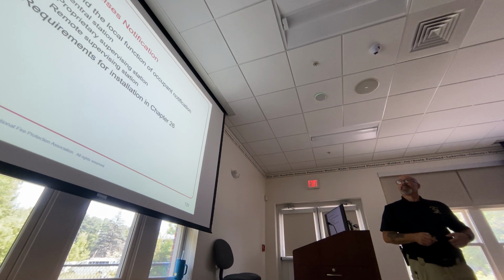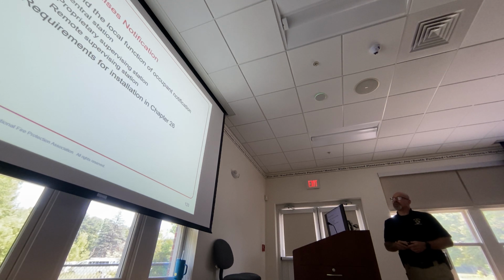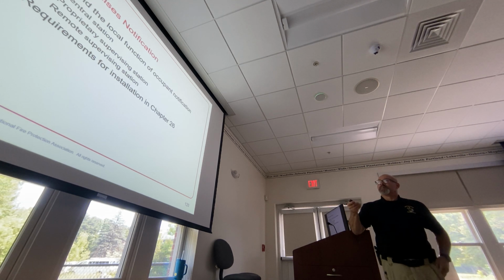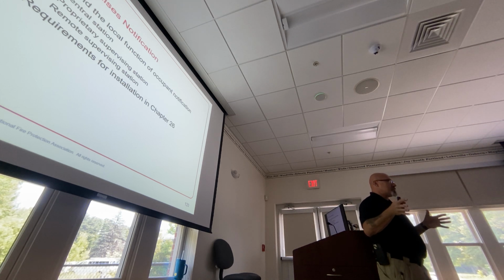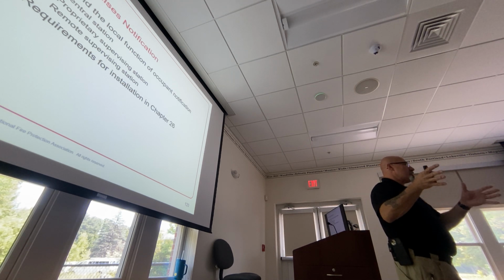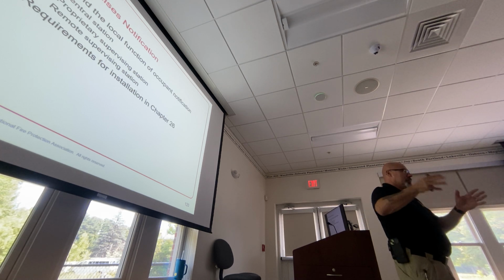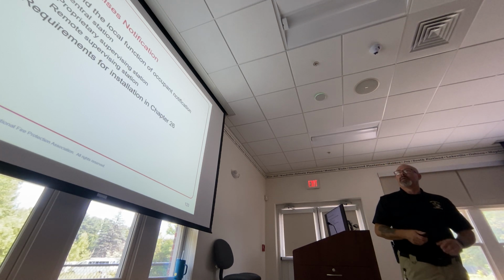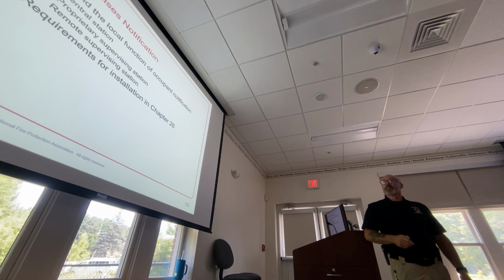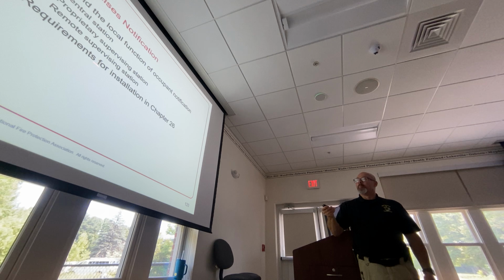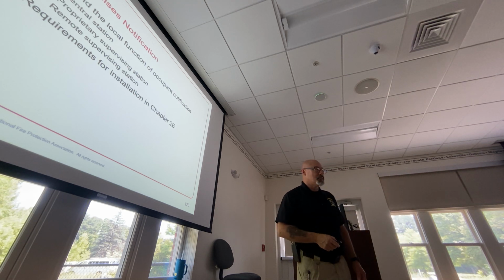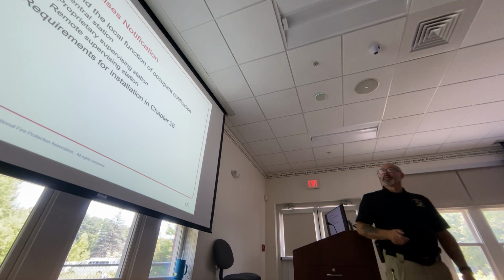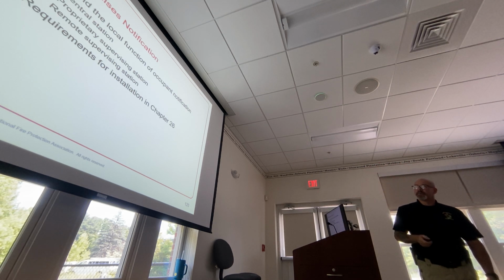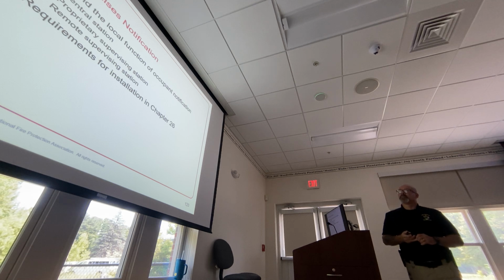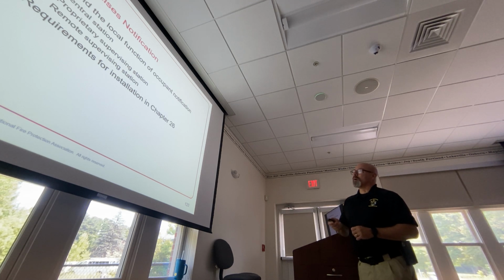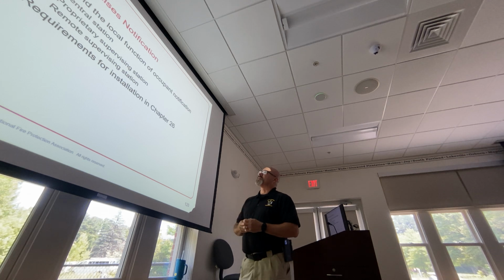Yeah, exactly, exactly. Off-premise notification. Central station, remember we talked about that fire alarm system. It's gonna call out and say, hey, we have an emergency here. Alarms are going off. Something's happened, troubles are occurring. It goes out to that central station. It could be a remote supervising station. It could be a proprietary supervising station. Okay, requirements for the installation of all that is in Chapter 26.